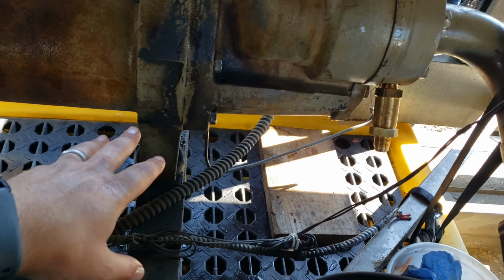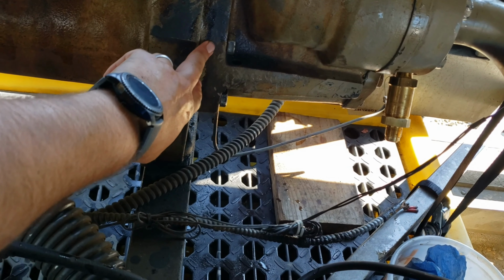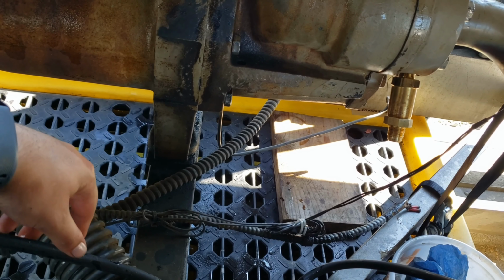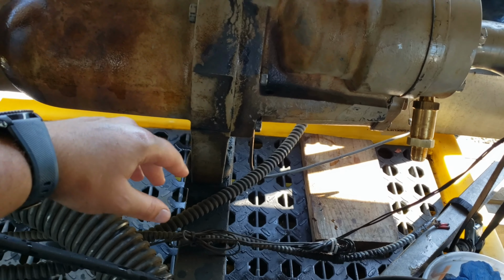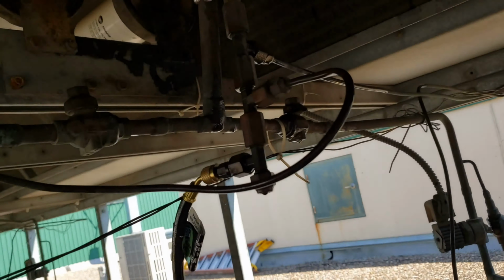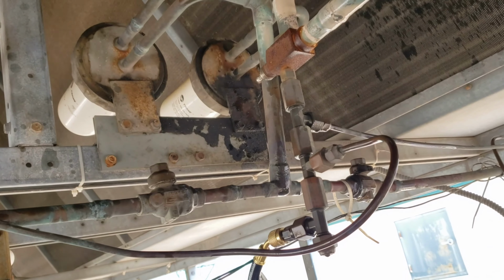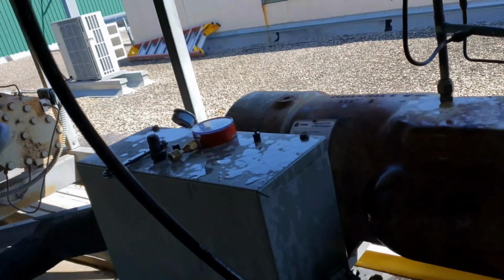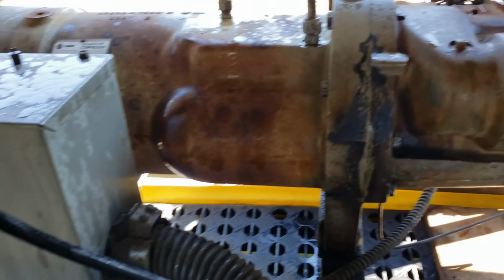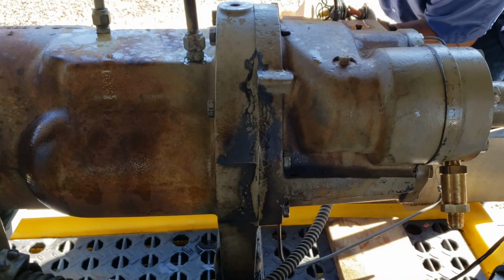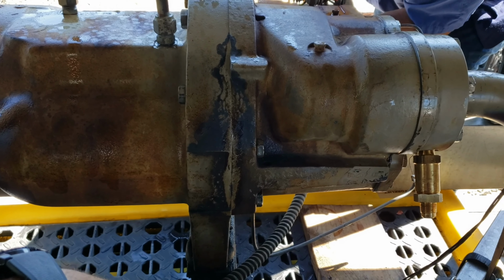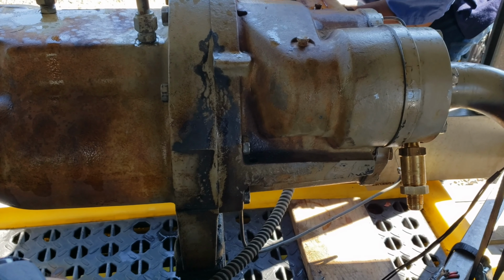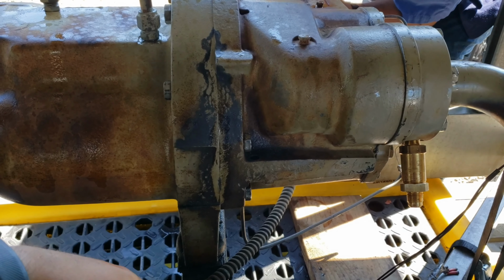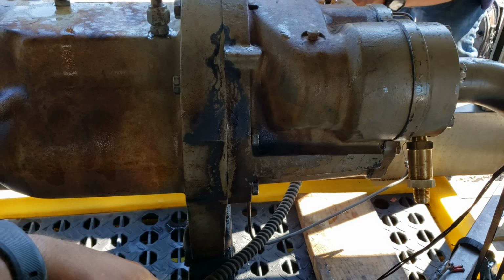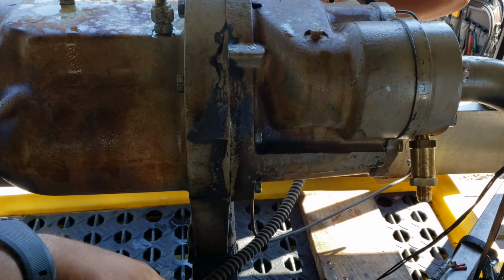This compressor was leaking oil from around this seal real bad. So we'll have to add some oil back to it. We're going to change the oil filters, take care of that, and then the customer is going to supply some refrigerant to make up whatever was lost through the leaks, and we'll get this thing back online.